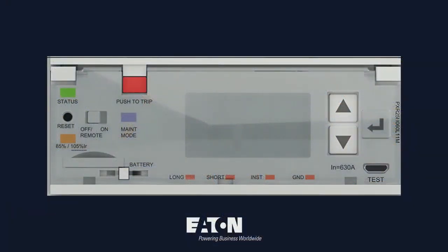So what that is, we have a maintenance mode on the breaker where you can flip the trip unit into a maintenance mode. That doesn't change any of the settings that you had before, but it allows the breaker to clear a fault much faster than it would if it wasn't in that maintenance mode, which reduces the amount of energy available, which makes it safer for whoever the maintenance person or operator is in front of the breaker. One improvement we made on that was before it was a 2.5x pickup, now it's 1.5x.